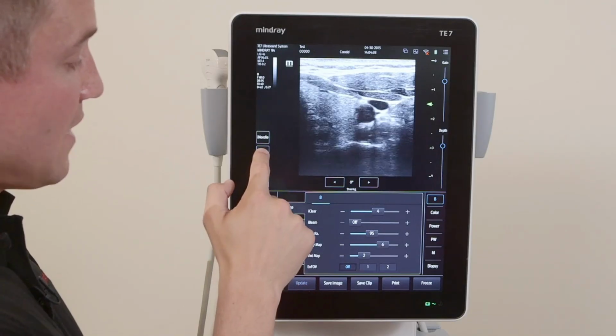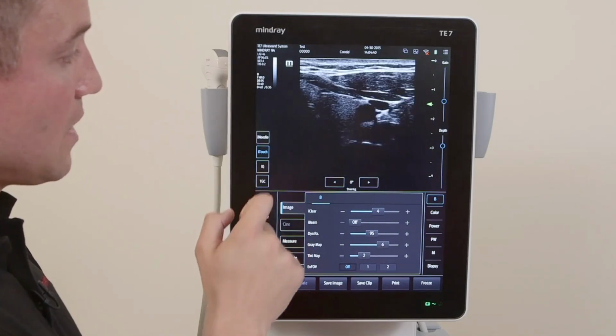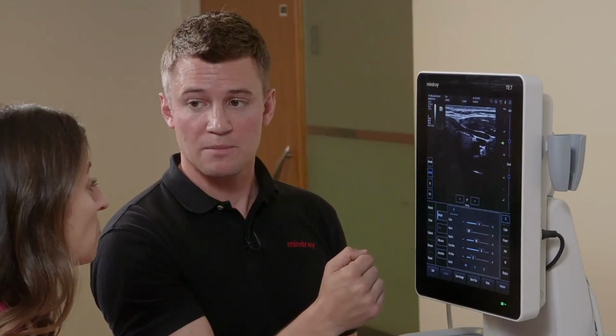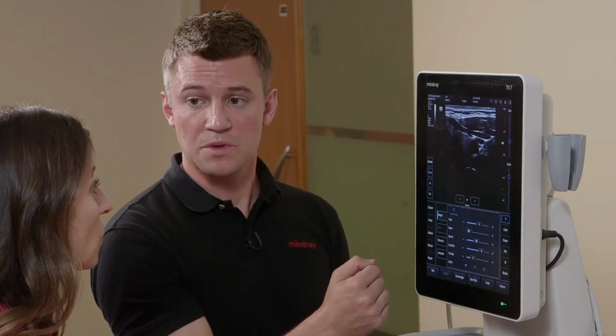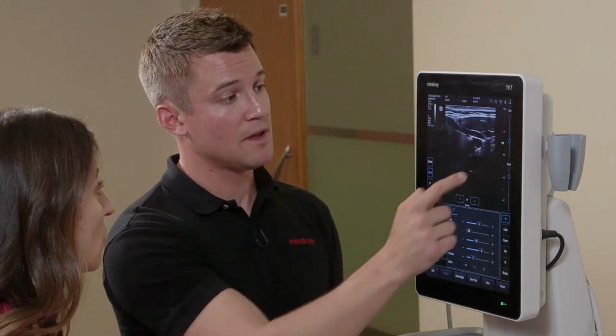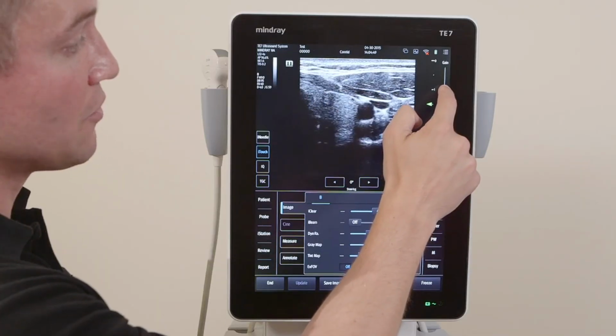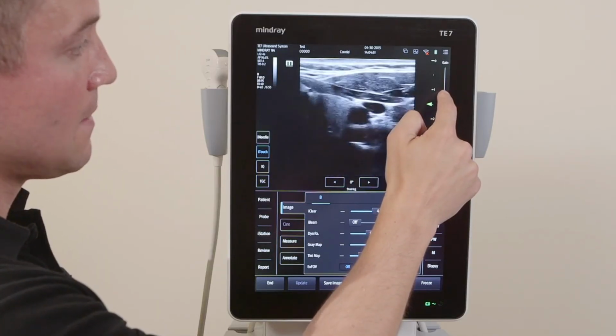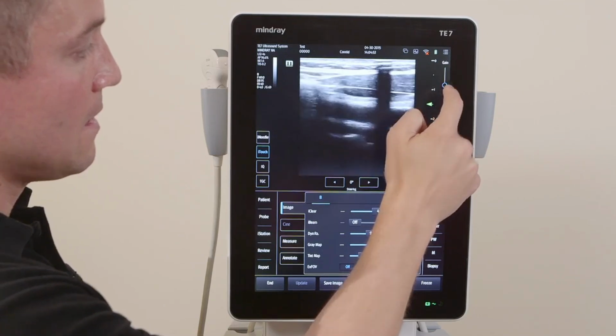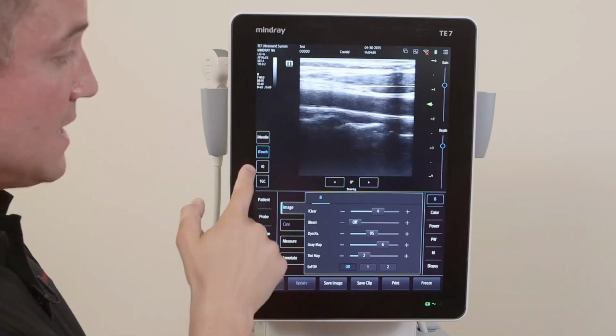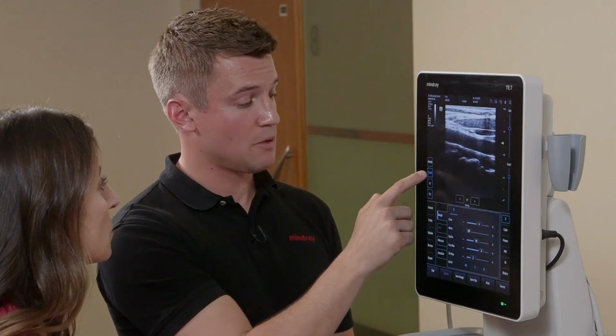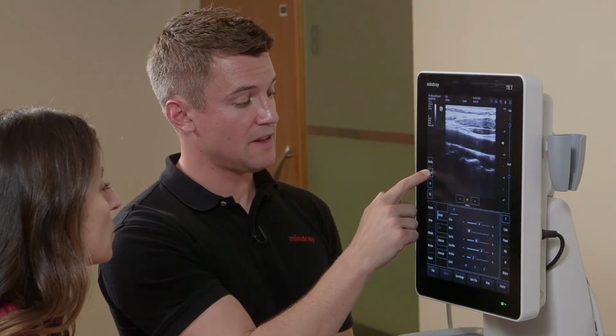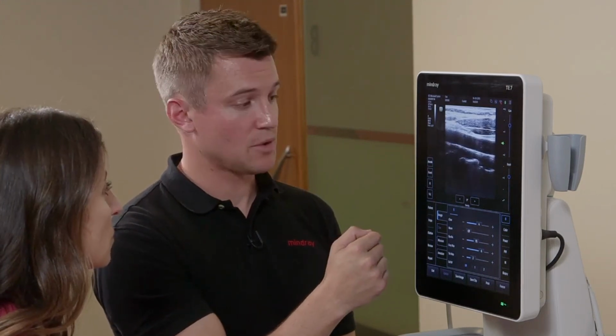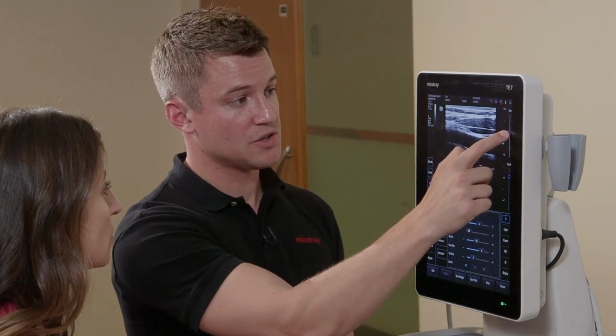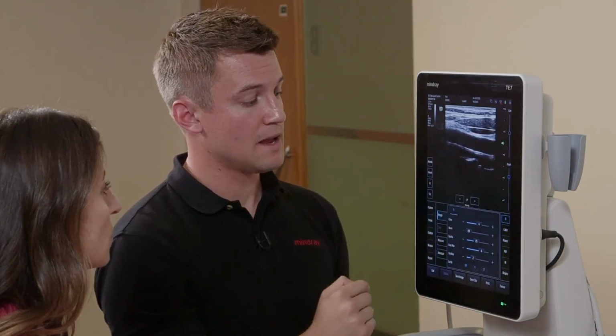Over here, we also have iTouch, which is our auto-optimize. When I press that, it auto-optimizes our B mode. It'll also work for the other modes, which we'll talk about as we move forward as well. You still have the ability to control your overall gain here on the right side. If you'd like to turn off the iTouch, again, which is our auto-optimize, I will press and hold the iTouch, and it'll flash, and it'll be disabled. Okay? You still have, again, the ability to control your overall gain.